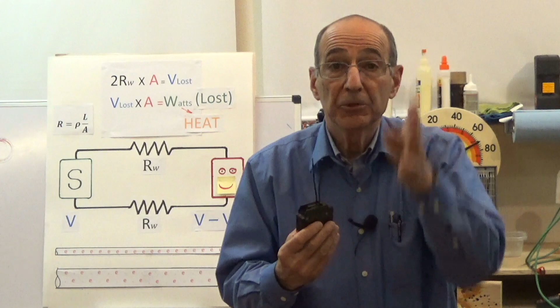Now you can make it thicker - there's no problem with it being thicker. It's a little harder to handle because it gets really stiff as it increases in diameter. But it can be thicker, it'll cost more, but it'll be safe. It mustn't be thinner - you don't want a wire that gets hot at 15 amps when the breaker isn't going to shut it off until 20.